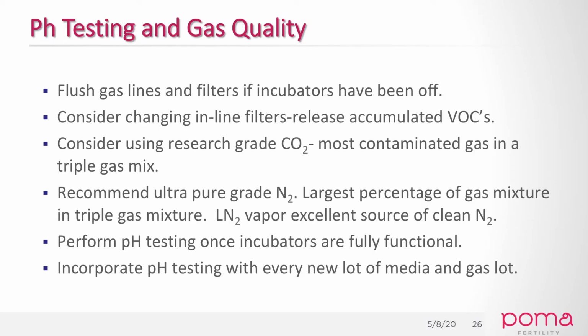So again, now let's assume your lab has been closed for a while. If it has been, this is a really good time to flush your gas lines and flush your filters out if your incubators have been off. You may even consider changing the filters that are in your laboratory. And the reason for that is that these filters have accumulated VOCs. So when you turn the gas on, depending on what the VOC load is on these filters, you could actually release a whole lot of VOCs into your lab.